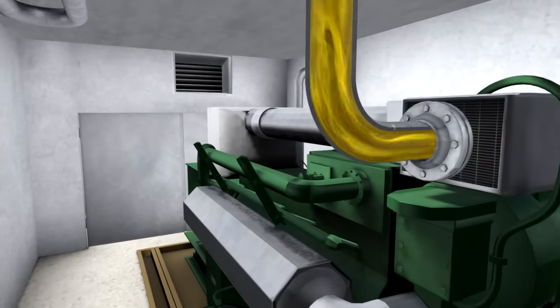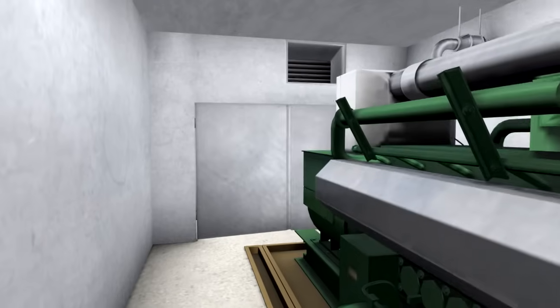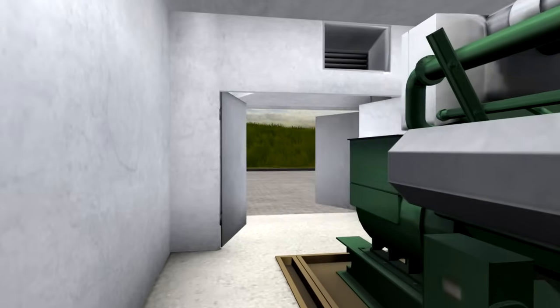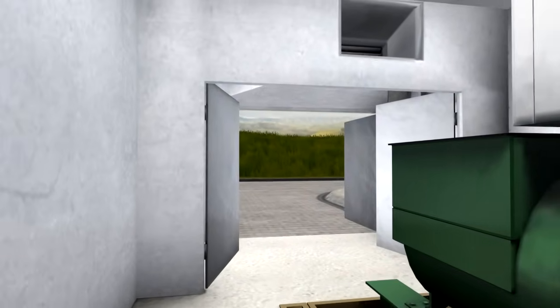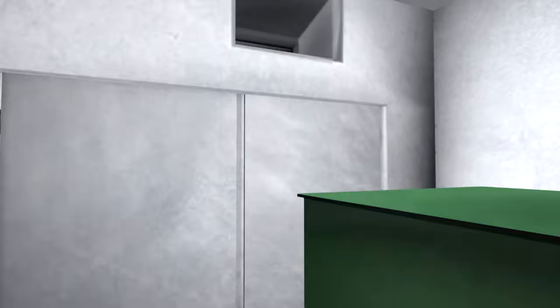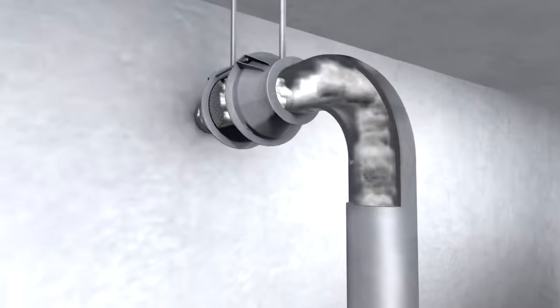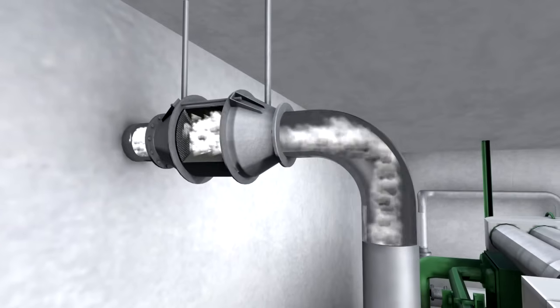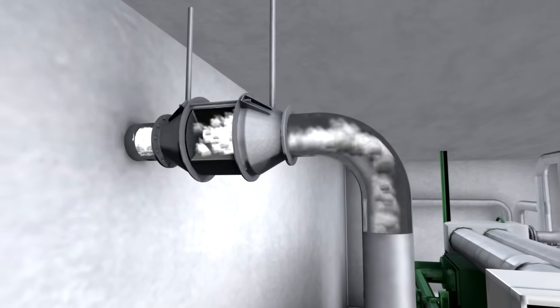In order to minimize noise emission, the CHP is located in a sound insulating cabinet within the plant room. The exhaust arising during the combustion process in the CHP passes through a catalytic converter developed specially for Envitech plants in order to reduce formaldehyde.